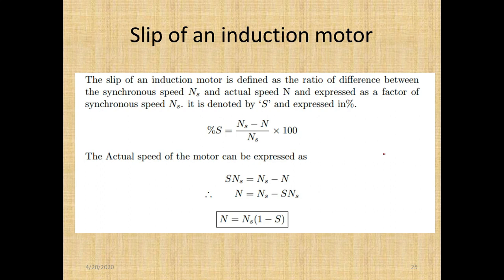After it experiences a force, the rotor part rotates with speed N, this is what we call the actual speed. The difference is the slip. The slip of an induction motor is defined as the ratio of difference between the synchronous speed Ns and actual speed N to the synchronous speed Ns, expressed as a percentage. %S = (Ns - N) / Ns × 100.